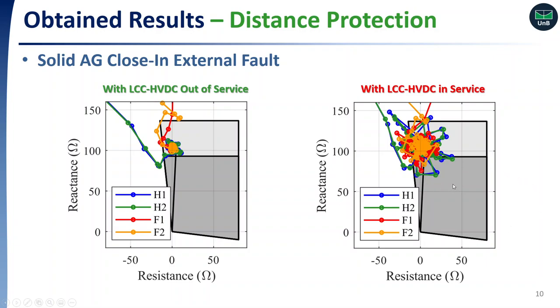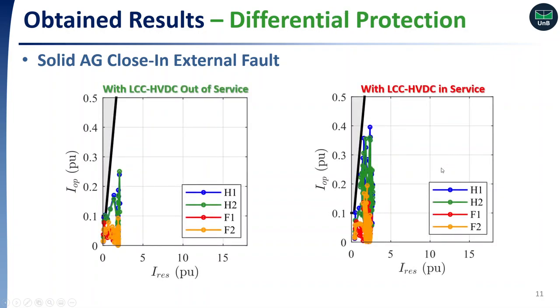Furthermore, as one can see, errors observed for half-cycle DFT-based algorithms are more significant than those obtained using full-cycle algorithms. Here we can see results for the differential protection. The differential protection remained stable regardless of whether the LCC bipoles are in service or out of service. In other words, differential protection was robust to errors on phasor estimation caused by the LCC-HVDC links' transient response in all evaluated cases.